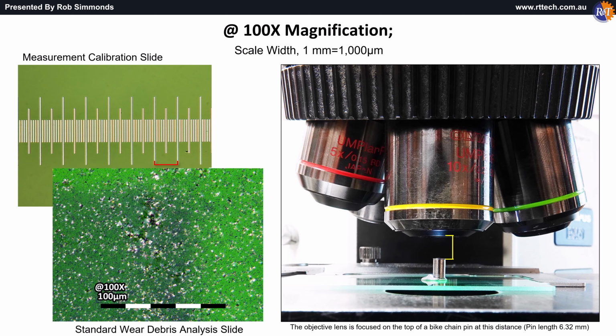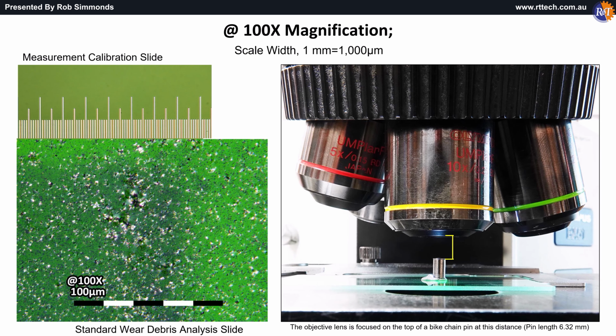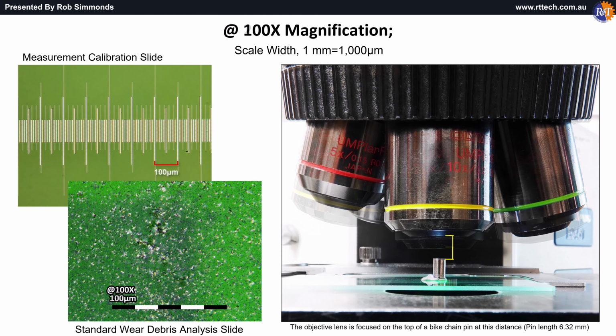The image at 100 times displays there is abnormal wear occurring and enables the particle count to be established. It's an ISO 4406 code, using the ISO 4407 5 and 15 micron microscope count. But there is not enough image detail yet to 100% diagnose the reason for the fine metallic particles.